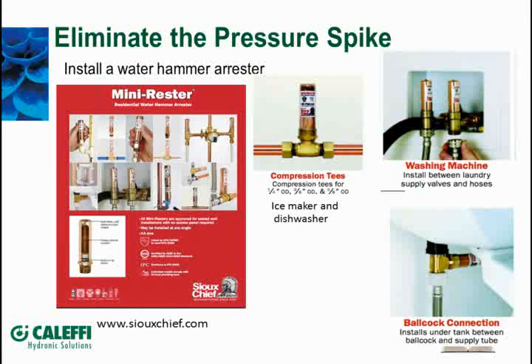But the other thing that causes that is if you have a pressure spike or a surge, and if somebody shuts off a valve quickly in a building, and you've got high water pressure especially, like 60, 80 pounds pressure, you can actually cause that spool to jump in there for a second. It's going to spit a little bit. And that can be caused by a water hammer. And water hammer is caused by a fast-closing valve somewhere in your system. And it's typically going to be like a wash machine valve. When it shuts off, you get that bang, that hammer.